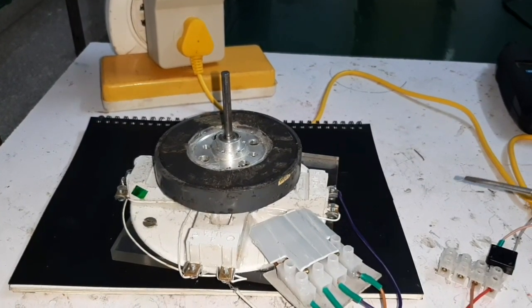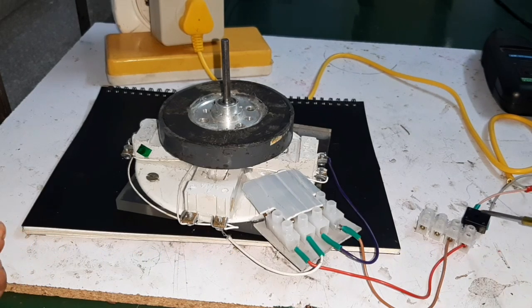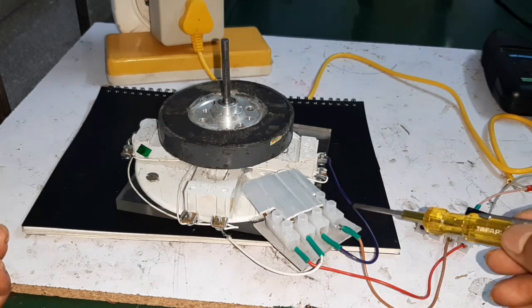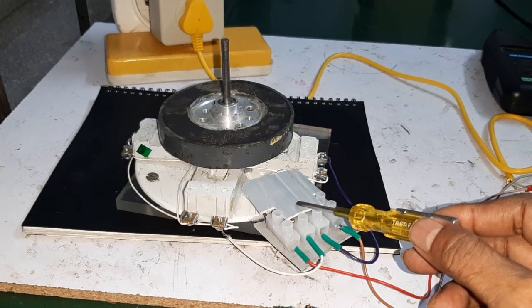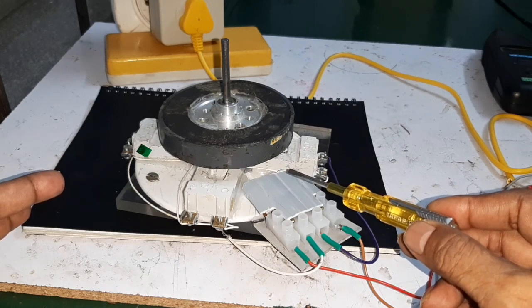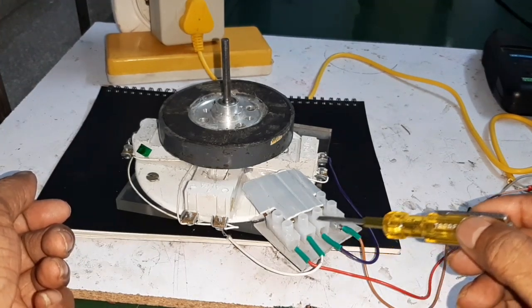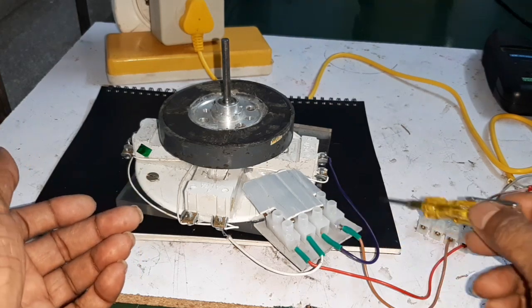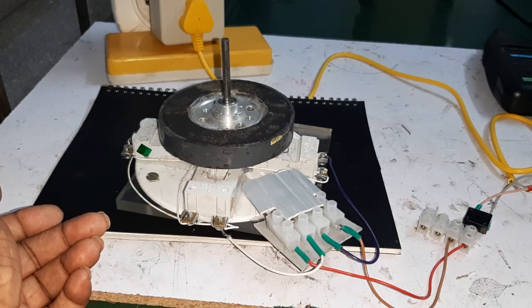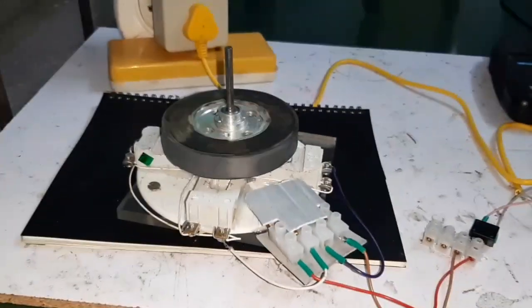Now I am going to test the motor with DC 230 volt. Here is the full bridge rectifier and the output is given to terminals one and four. This is the dual actuator which controls the BLDC motor with both AC and DC. I am now connecting DC 230 volt supply to terminals one and four, and terminals two and three are the output connected to the motor. The motor is running.